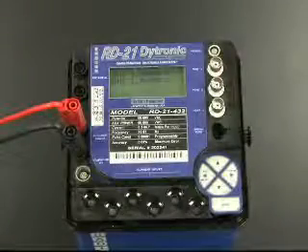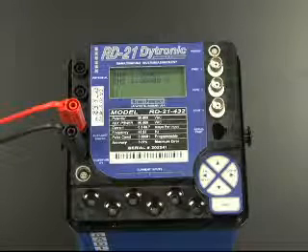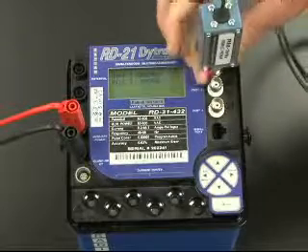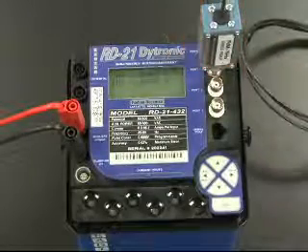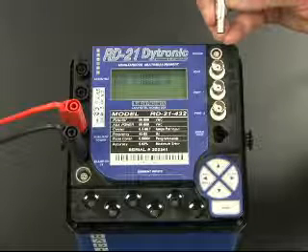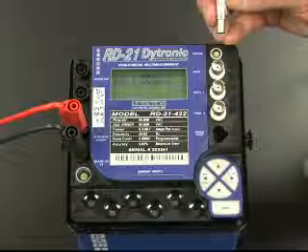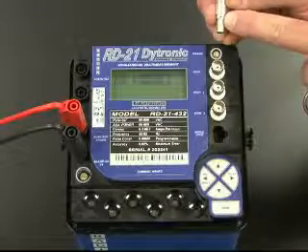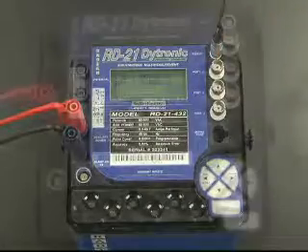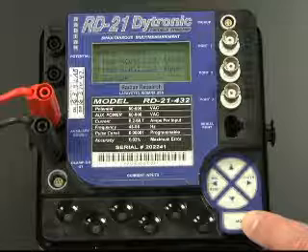Radian manufactures 2 types of sensors compatible with the Dytronic series of standards, the RM series and the RD series. The RM series of sensors will connect to the standard via the port 1 BNC connector, while the RD series of sensors will connect to the 4-pin LEMO terminal, labeled Pickup. When connecting the sensor to the LEMO port, be careful to correctly align the red dots on both the sensor and the pickup terminal. Press Mode on the keypad until the main menu is reached.